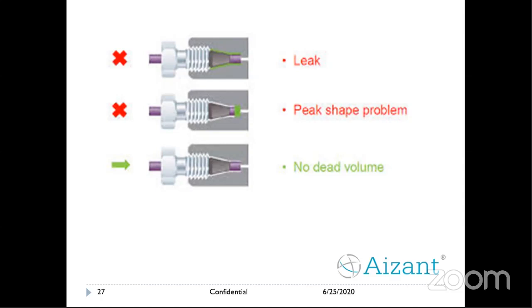The second part also shows a peak shape problem. You can see that an additional void has been created if the ferrule heights are not proper, or not as recommended for the system or the column. You will end up with a void generated at the head of the column, and again at this end your sample components will accumulate, and you can see multiple issues.